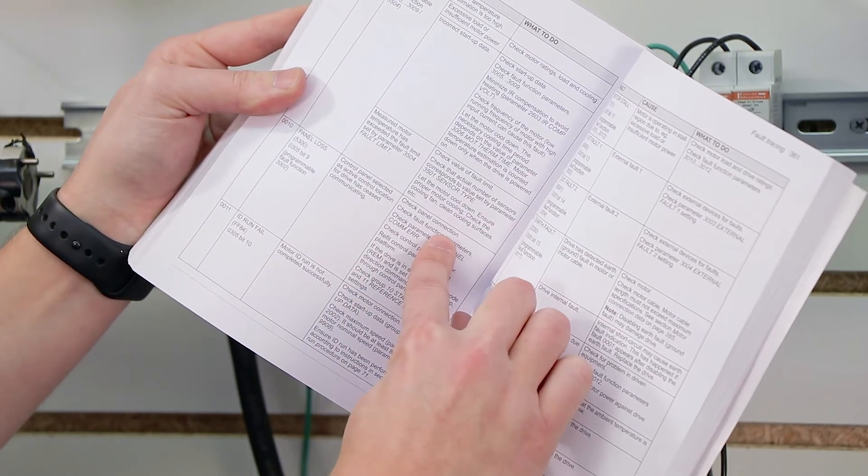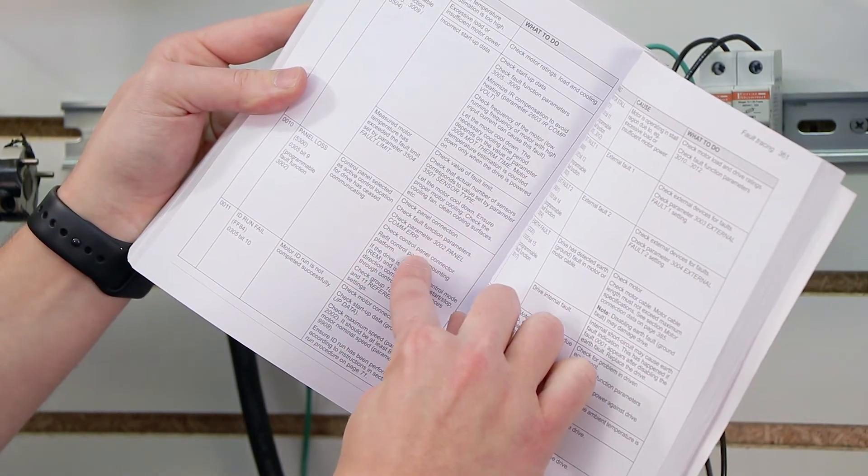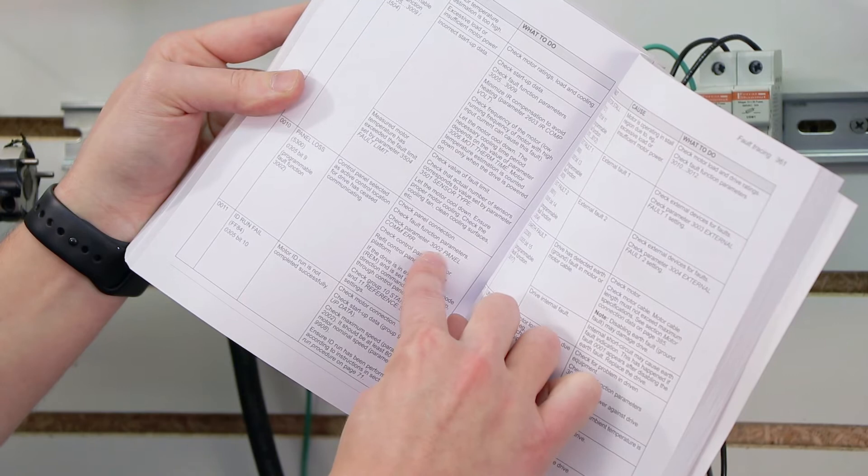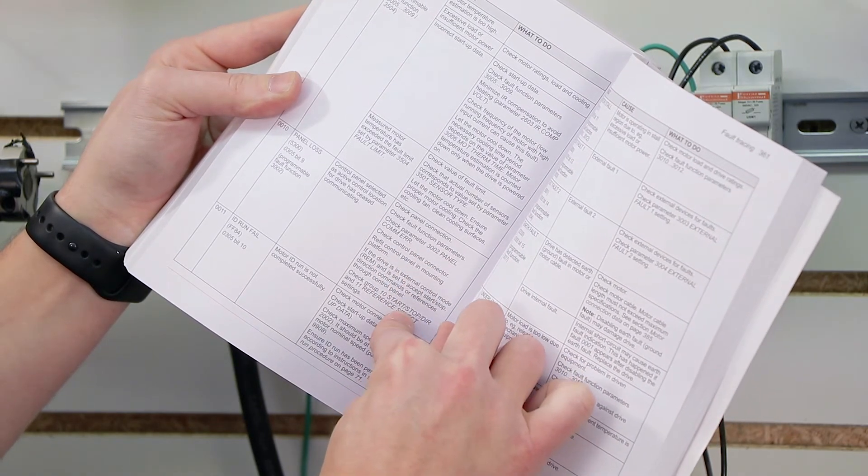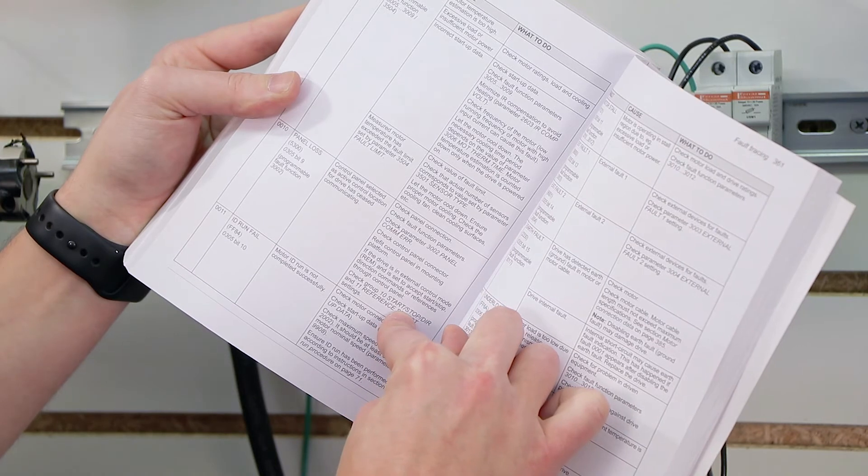We can check the panel connection, check the fault function parameters, check a certain parameter 3002 for the panel comm error. Essentially, they're giving me a whole list of suggestions to make that error message go away.